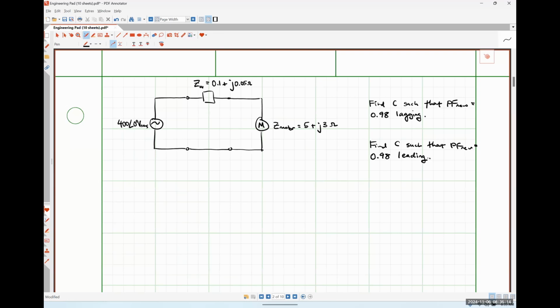The utility doesn't care if your power factor is leading or lagging, they just want it close to 1. So if our threshold for the electric utility is a power factor of 0.98, anywhere from 0.98 lagging to 0.98 leading would be acceptable.